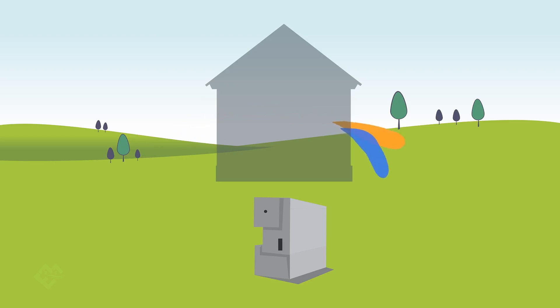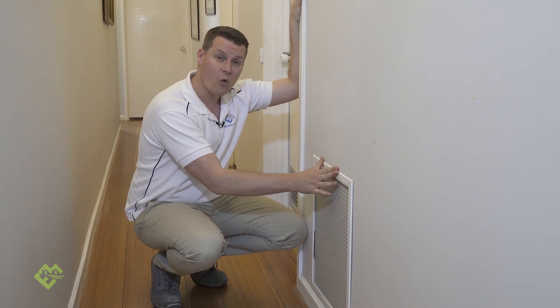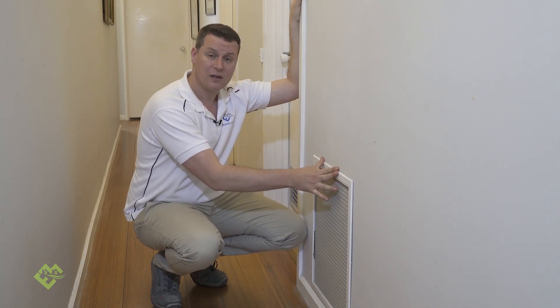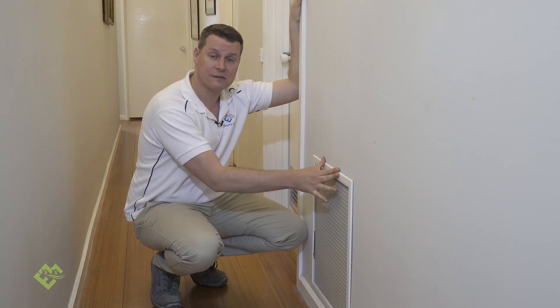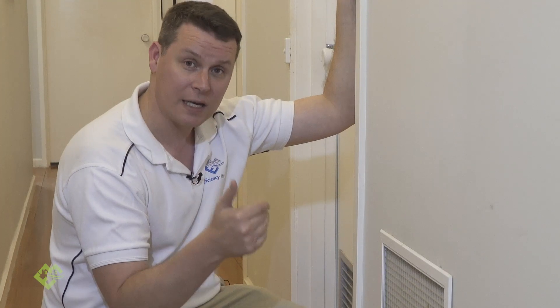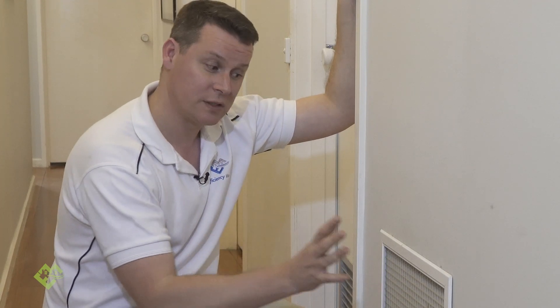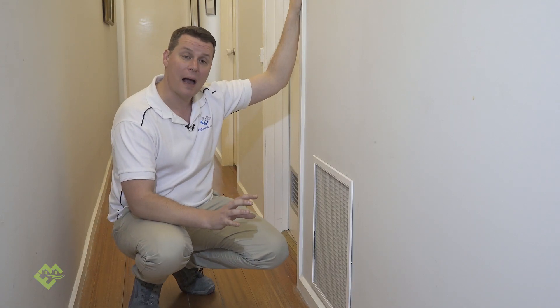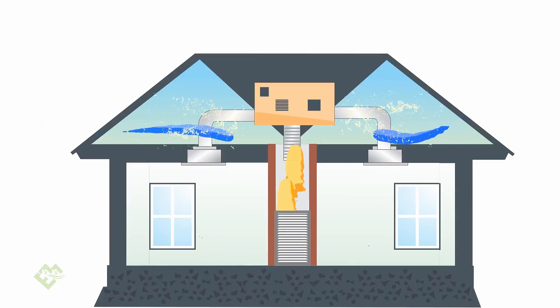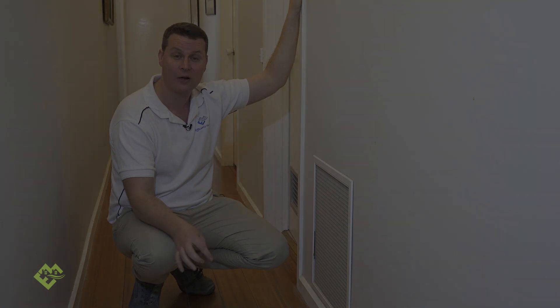The other important thing when it comes to ducted heating is having all your doors open. Your supply vents need to be able to get air back to the return. As soon as you start pushing air directly to the outside via rooms where the door is closed and you might have wall vents, it's going to start drawing in air wherever it can on the return side. Economically, you could be paying an extra two hundred dollars a year for having one of these ducted heating returns completely open to your roof void or underfloor.